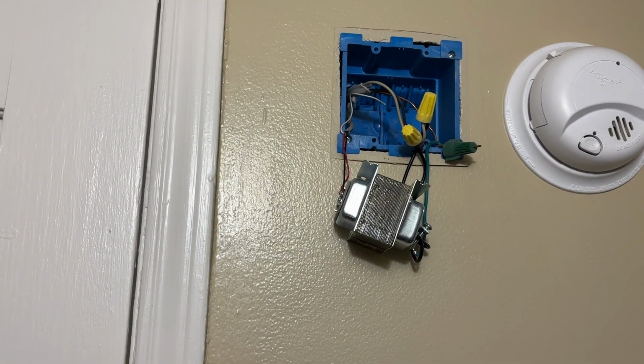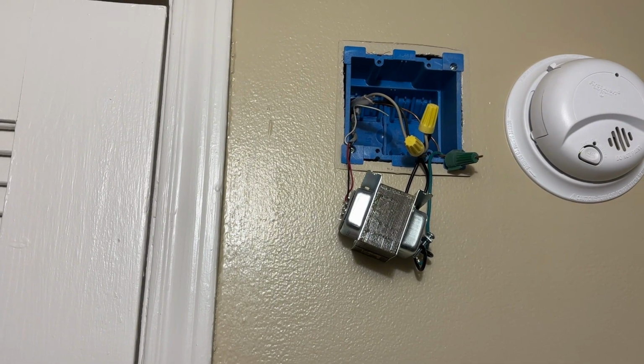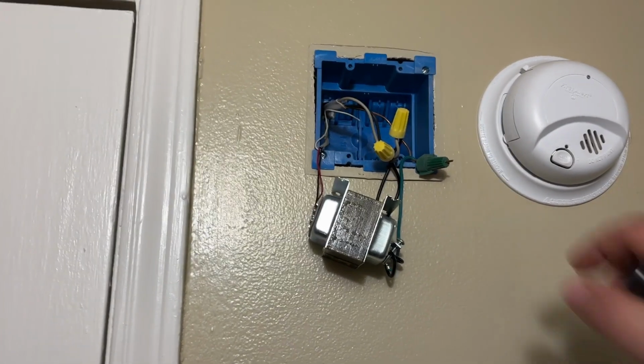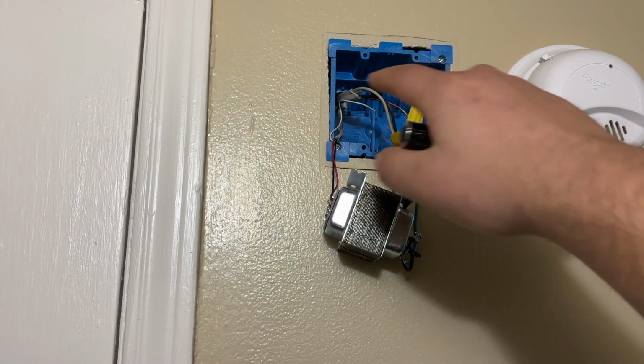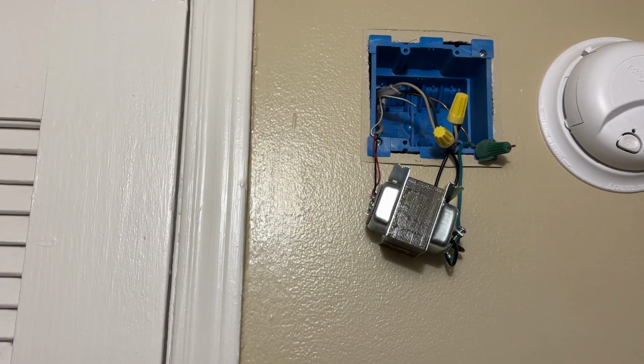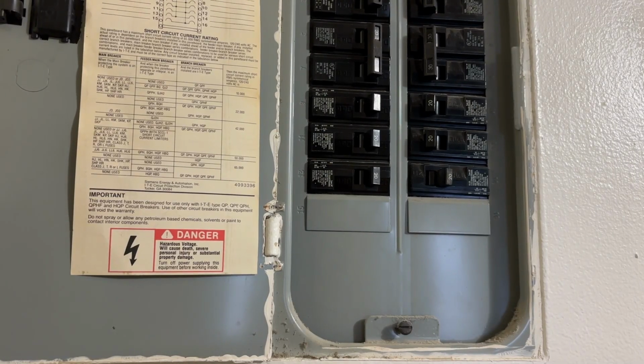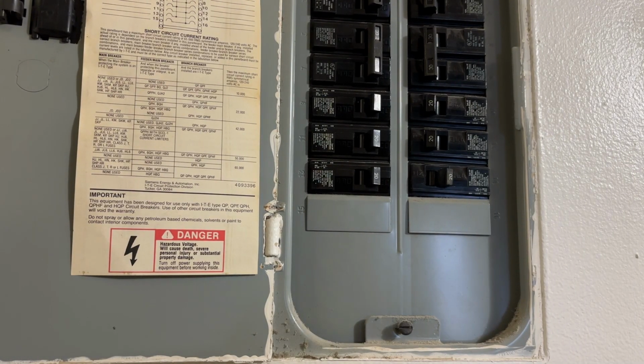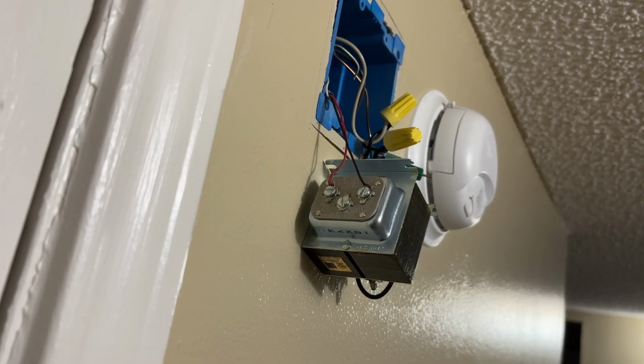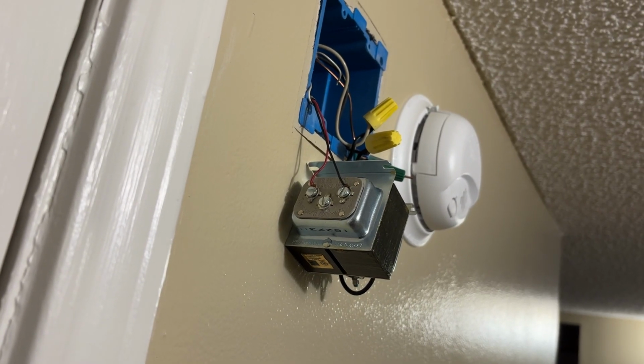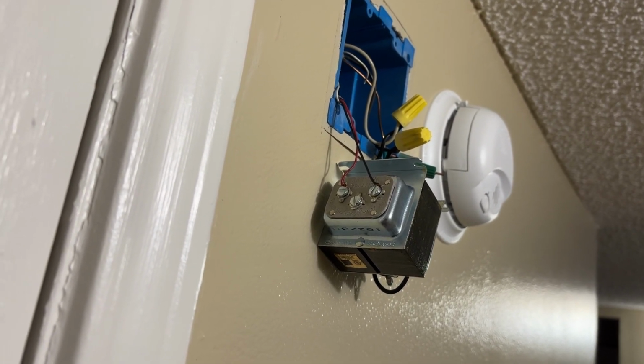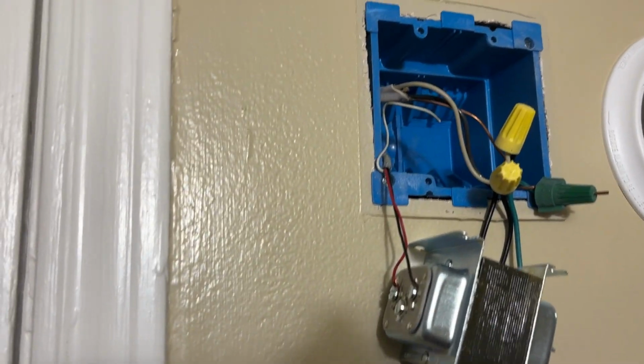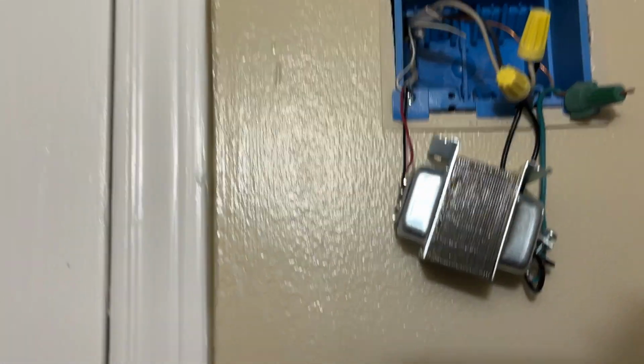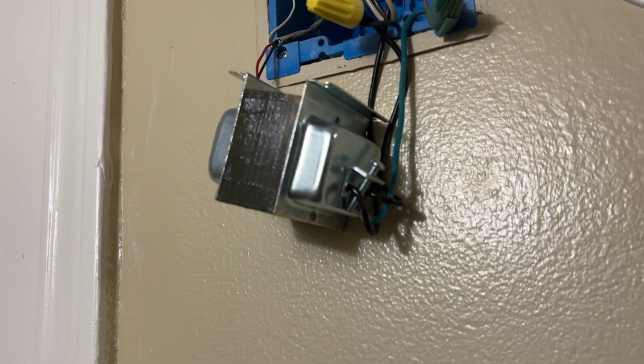While the breaker is off, we can remove our transformer, leaving the wires attached, separating the wires and making sure there's nothing touching any metal or anything that could possibly cause a short. Once we verified that no wires are touching, we can return power to our transformer. On our transformer, we can see our 2 low voltage wires. In this case, we're using black and red. We have a third white that is rolled up that's not being used on the low volt side. And on the back side, we will have our line, neutral, and ground.